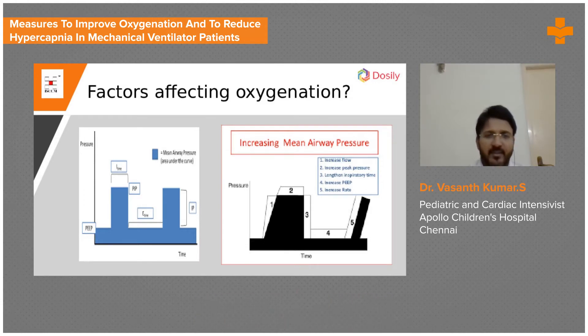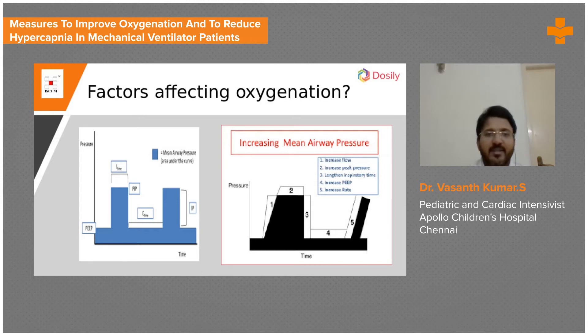Here you can see a square waveform. A square waveform can be a flow-time scalar or a pressure-time scalar. Because there is no negative deflection, this is definitely not a flow-time scalar — so this is a pressure-time scalar with a square waveform in pressure control mode, where the pressure is constant.